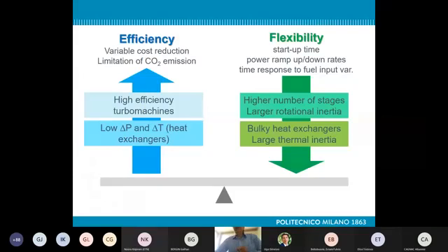Finally, we wanted to answer the initial question due to the flexibility of the CO2 potentiality. And so we have to find a compromise between efficiency and flexibility, and to demonstrate that the plant is quite fast to follow the loads. Indeed, if you want to maximize the efficiency, you have to use high efficiency turbomachines, so a high number of stages, for example, and heat exchangers with low pressure drops and low temperature differences. That will lead to quite big turbomachinery and quite big heat exchangers that will lead to an increase in the thermal inertia. So that seems to be in contrast. So the dilemma is between efficiency and flexibility, but it is possible to find a good compromise.